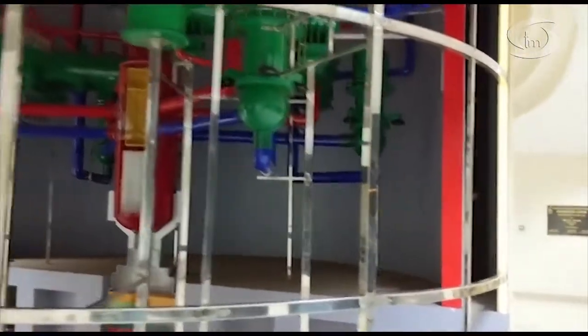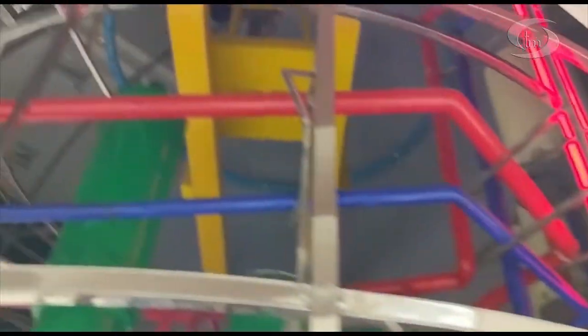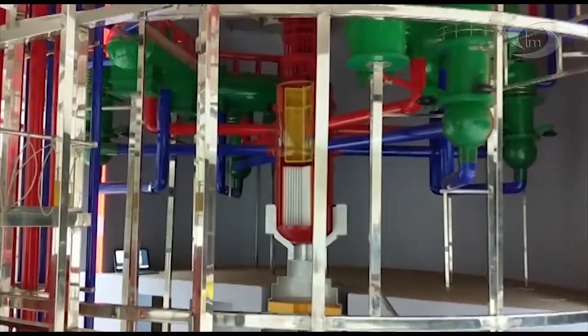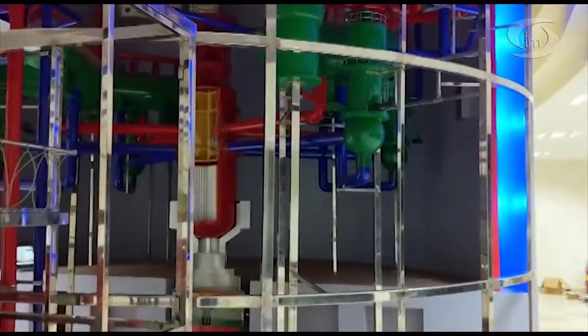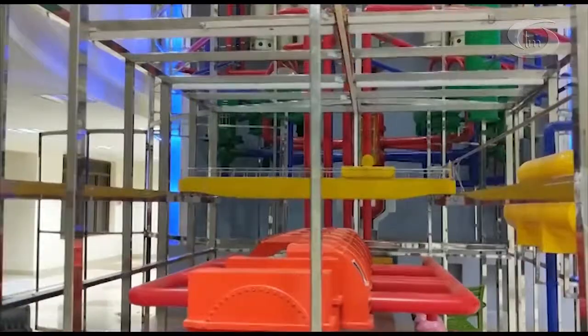Now it is time to understand the state-of-the-art safety features and other important components. The reactor building is actually a two-containment structure. The outer containment is a reinforced cement concrete structure two feet thick, protecting the reactor from external threats. The inner containment is four feet thick and made of pre-stressed reinforced concrete — it protects nuclear components and helps contain radiation within the building. Between these walls, a gap of two meters is kept at negative pressure, ensuring no radioactive particles escape to the outside.